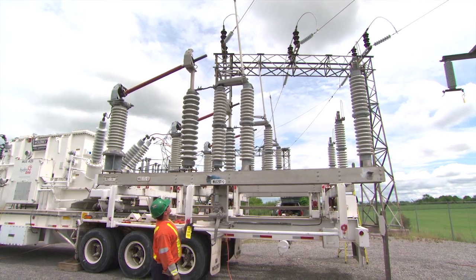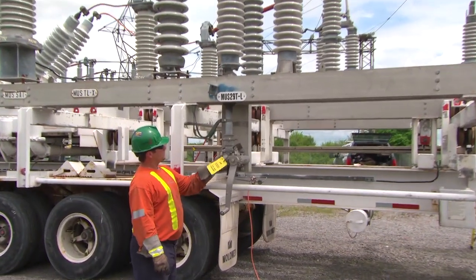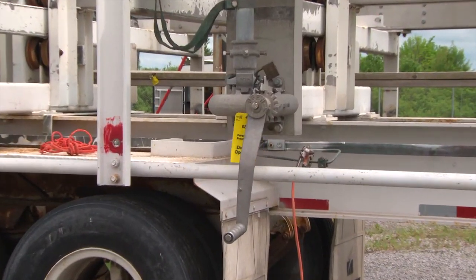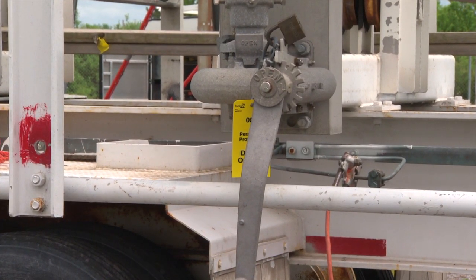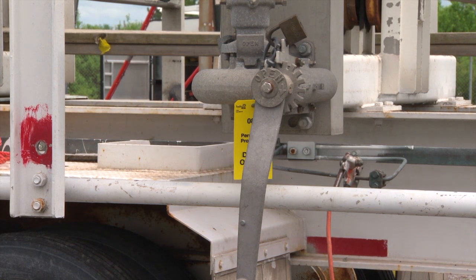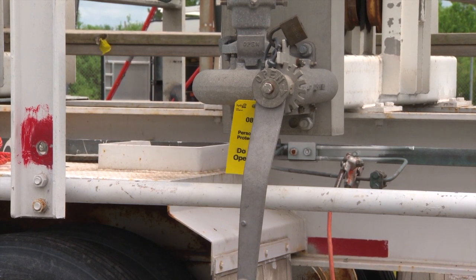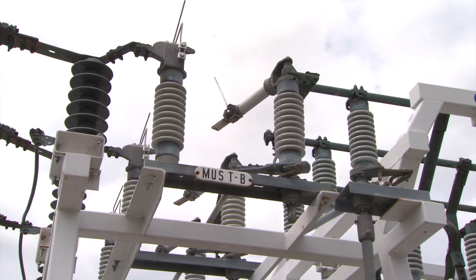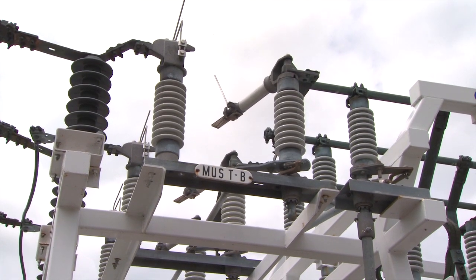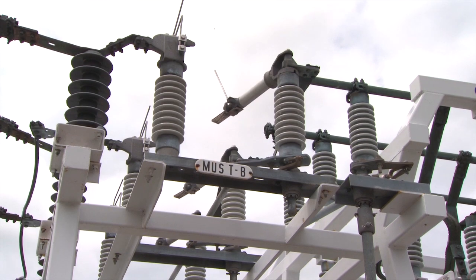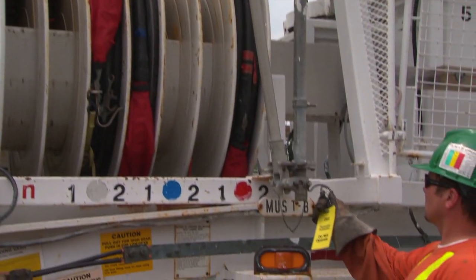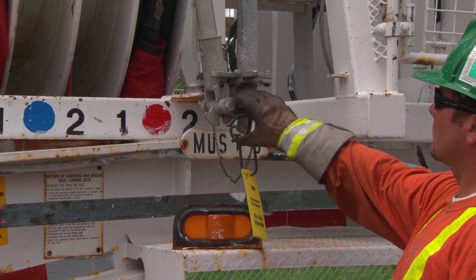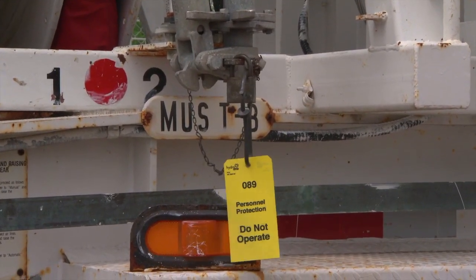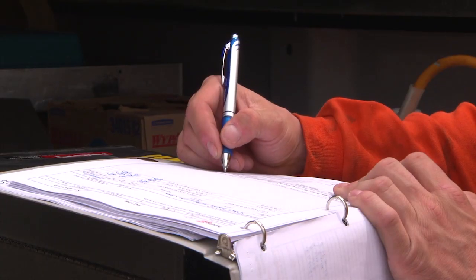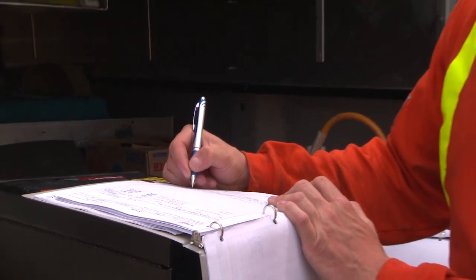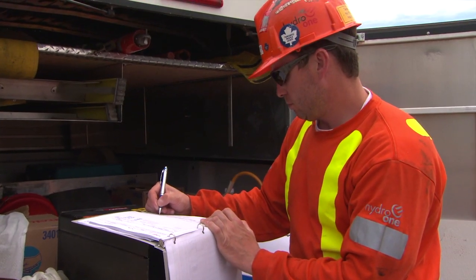Check all 3 phases on the MUS T-L high-voltage switch are open and leaning back. Lock and tag the operating handle. Check all 3 phases on the MUS T-B low-voltage switch are open. Lock and tag the operating handle. The permit is accepted once all 3 steps on the PC-17B have been completed.